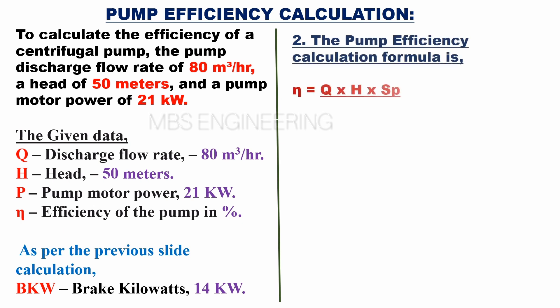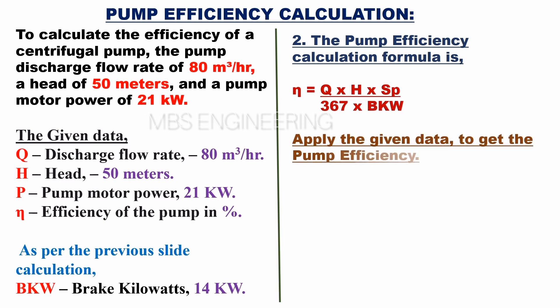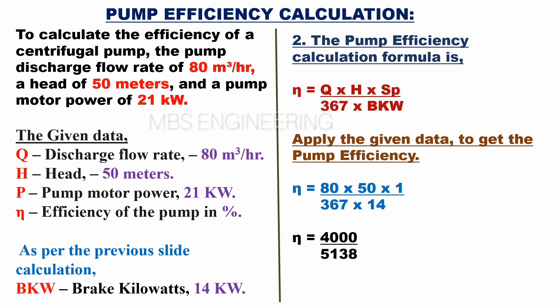Pump efficiency Eta equals Q into H into SP, divided by 367 into brake kilowatts. Applying the given data: Eta equals 80 into 50 into 1, divided by 367 into 14. Pump efficiency Eta equals 4000 divided by 5138. Therefore, the pump efficiency Eta is 77.85%.